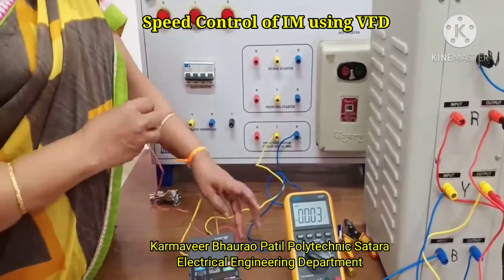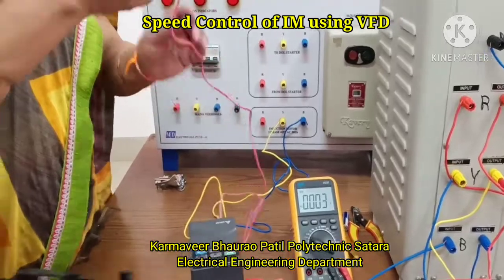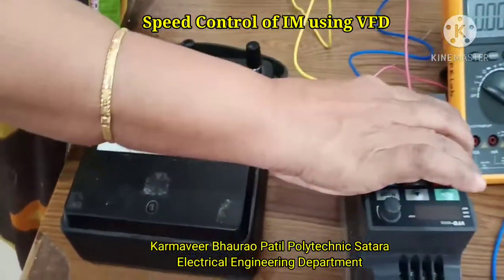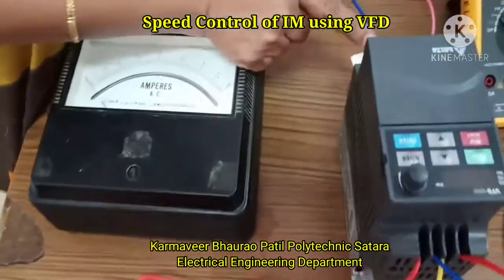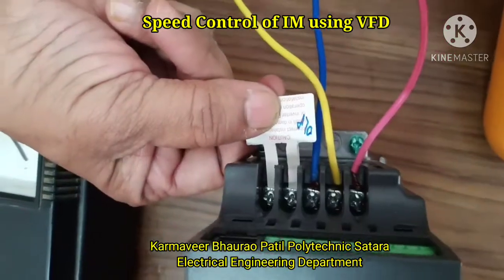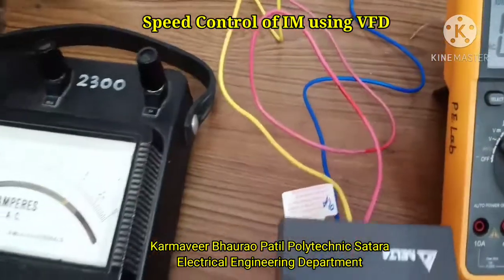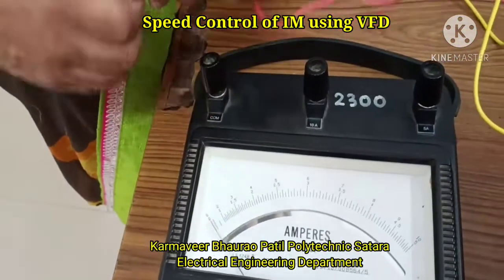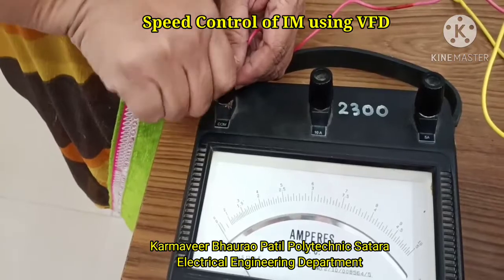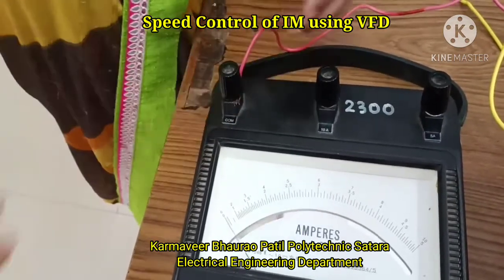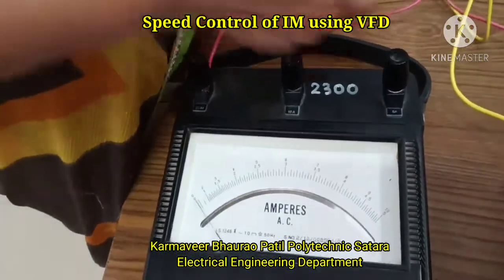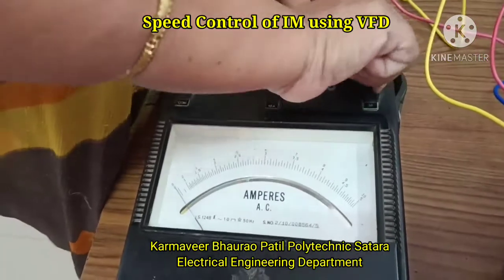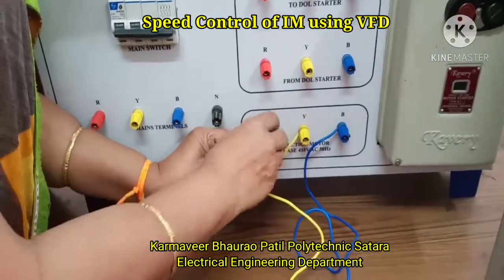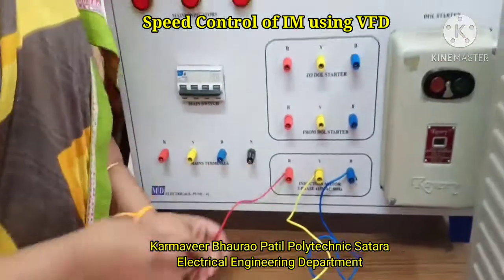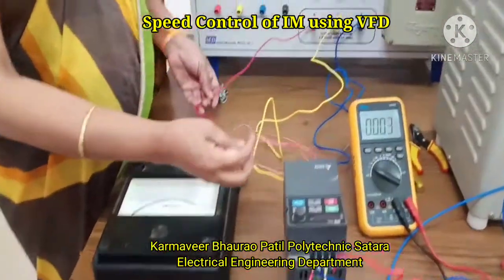We just want to keep a watch on the current. We are not taking a reading for current, but only to see whether proper current is flowing. This is the output of the R phase, and we have marked it here as output. So the output R phase will be connected to the common of the ammeter, and then its 5 ampere range terminal will be connected to the R phase of the stator of the squirrel cage induction motor. That way, the output of the VFD is connected to the R phase through the ammeter.